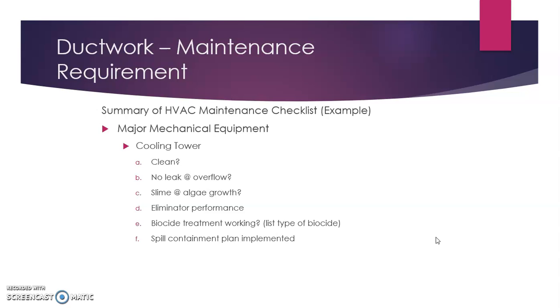I believe that during the visit to the campus technology chiller plant room, we visited the cooling tower at the rooftop. And then the eliminator performance, how about that? And then whether the treatment is working or not, the biocide treatment, and then whether there is any spill or containment plan implemented there.